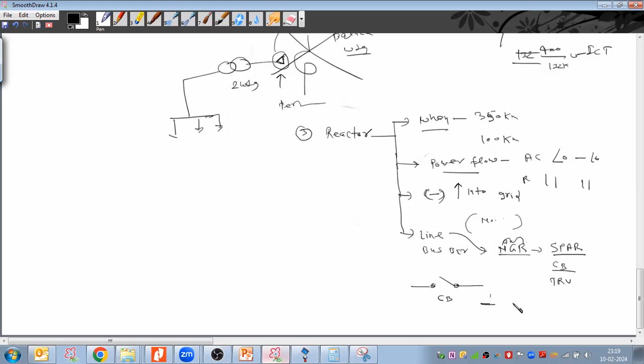Means when the circuit breaker poles are separating, during the pole separation a transient voltage will form. If the transient voltage is forming across the breaker, then even though the breaker is isolated, it is not really isolated: the arc current, the arc, will be present between both the moving and the fixed pole. So we need to minimize that arc current and this transient recovery voltage. This facility is provided by the NGR. I'm telling you NGR is required, but do not just follow my words. I'm telling this on the reference of IEC 60076, part number 6, page number 92.